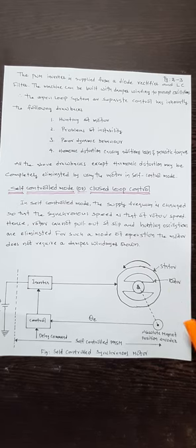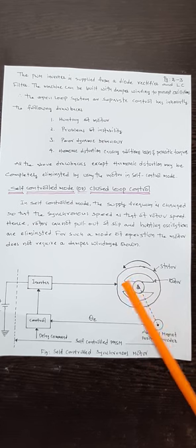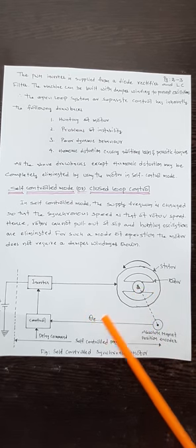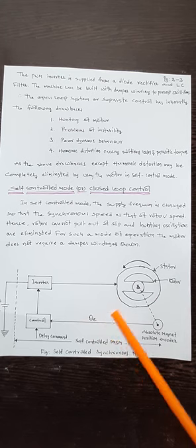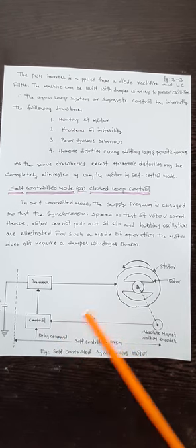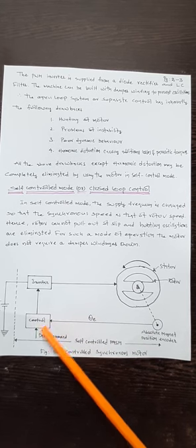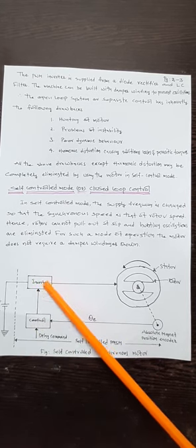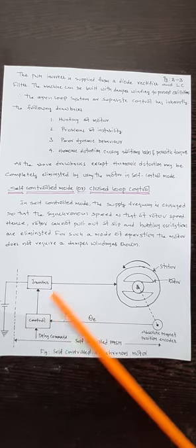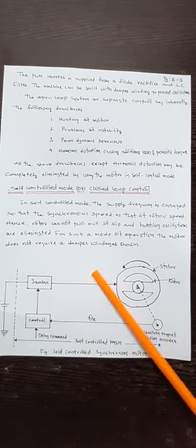Here, such type of problem is almost eliminated. Why? Because if there is any minute variation of the speed between stator as well as the rotor, this absolute magnet position encoder senses that, and detects the difference, this error, between the stator as well as the rotor speeds. This is processed through the control circuit to the inverter. The inverter control circuit may obviously use PWM techniques to change the V by F control.